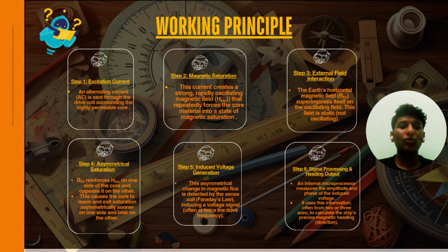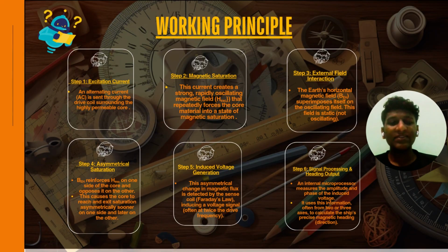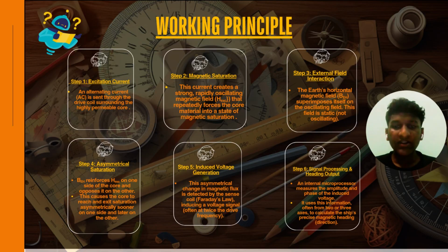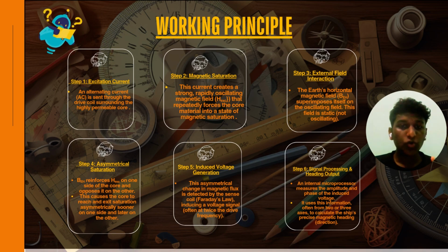So next, the working principle of the fluxgate compass. Here I explain it step by step. Step one, excitation current. An alternating current (AC) is sent through the drive coil surrounding the highly permeable core. Step two, magnetic saturation. This current creates a strong, rapidly oscillating magnetic field, H_AC, that repeatedly forces the core material into a state of magnetic saturation.